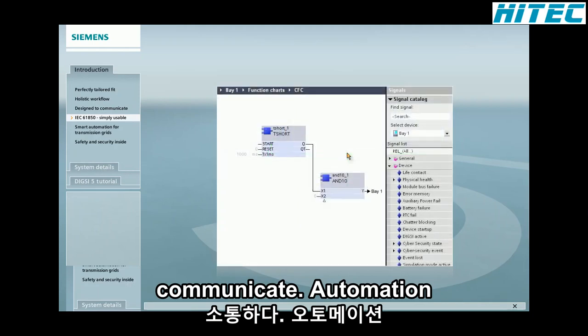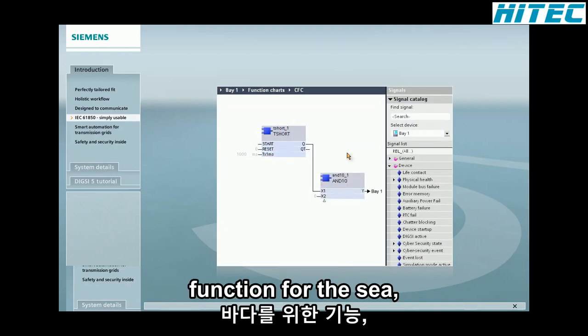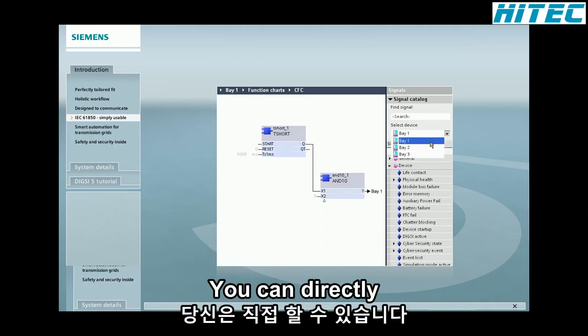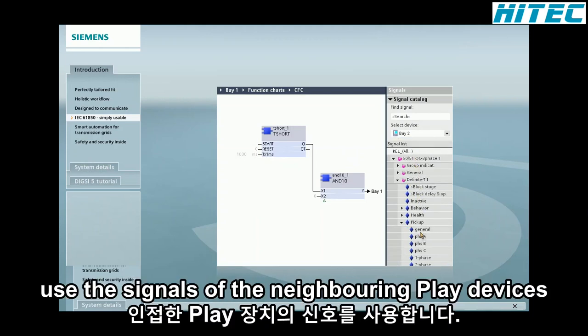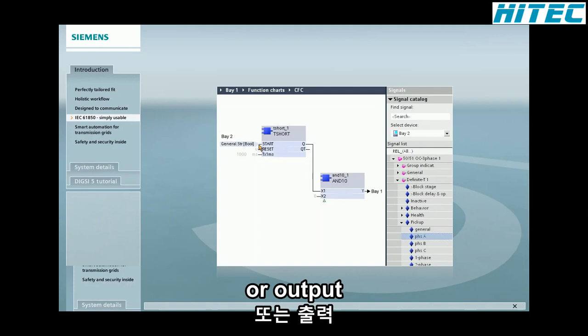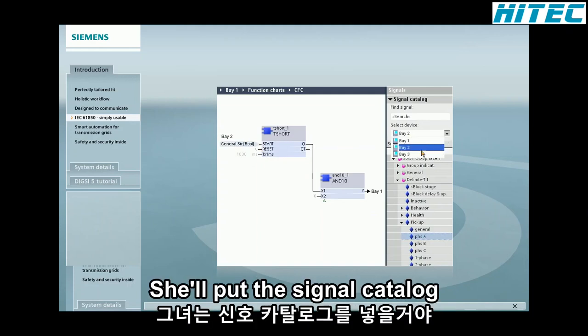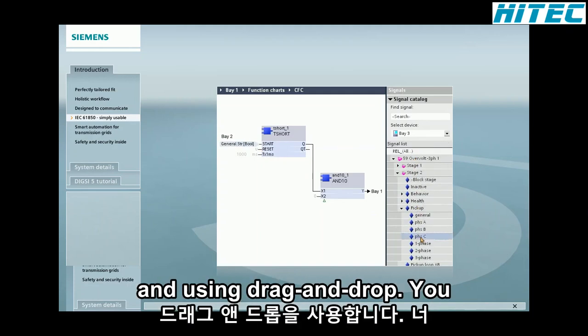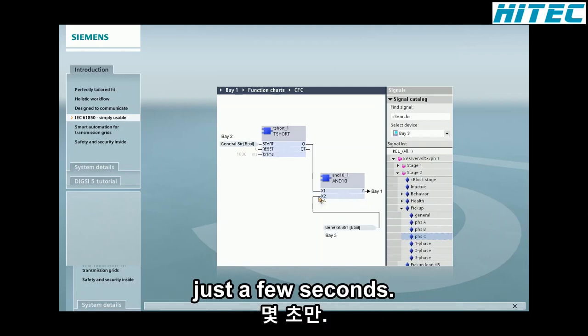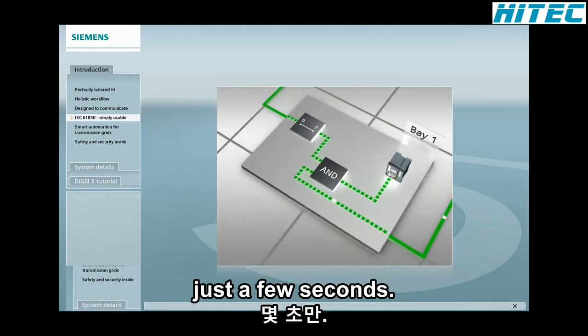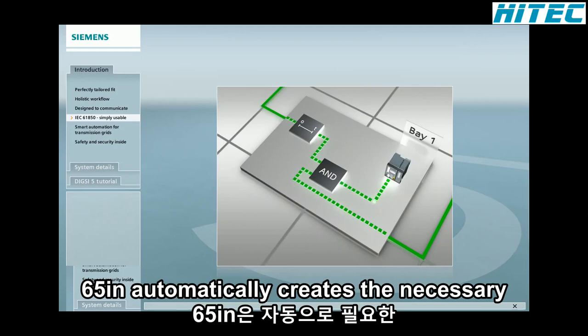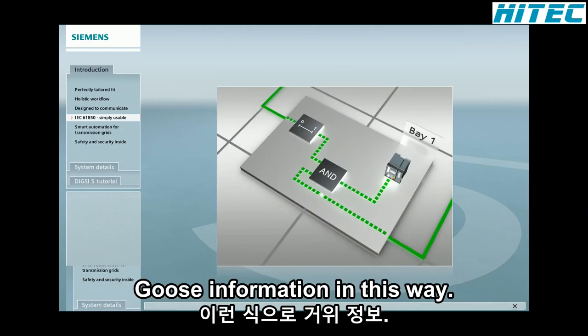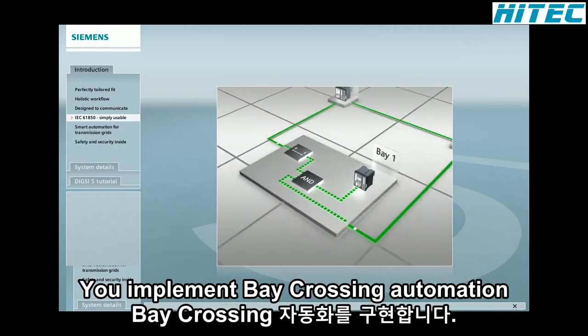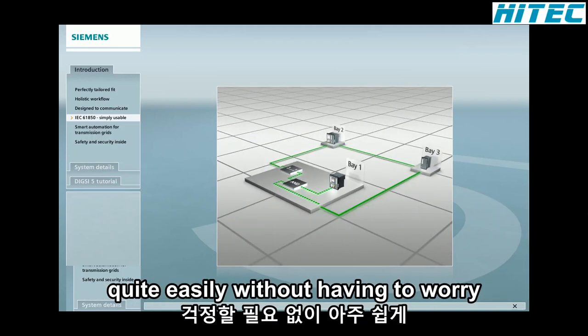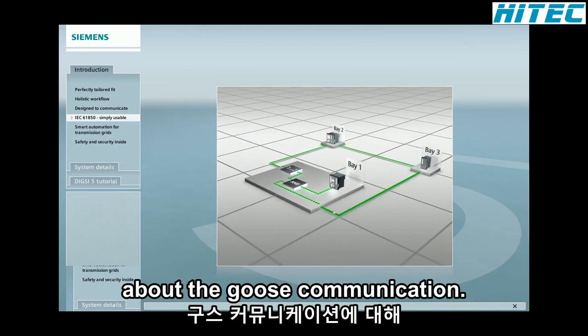When, for example, you create an automation function for the SIPROTEC 5 device in Bay 1, you can directly use the signals of the neighboring bay devices as input or output information. With the help of the signal catalog and using drag and drop, you take care of this in just a few seconds. DIGSI 5 then automatically creates the necessary GOOSE information. In this way, you implement bay crossing automation quite easily without having to worry about the GOOSE communication.